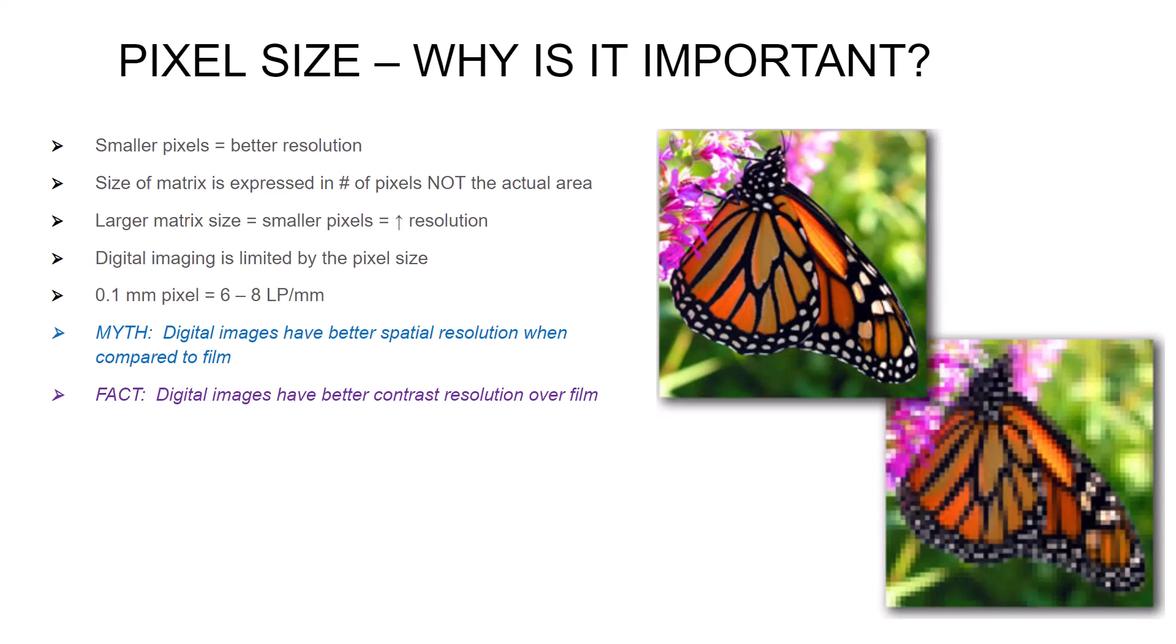So why is pixel size so important? Smaller pixels means you'll have better image resolution. The size of the matrix is expressed in number of pixels, not the actual area in terms of length and width. It's the number of pixels. Given the same field of view as in these two images on the right, having a larger matrix size means you'll have smaller pixels and better resolution.